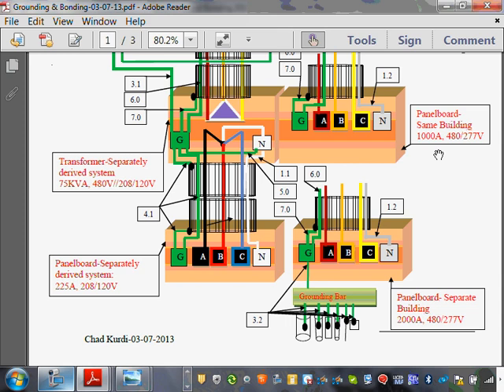So that's the only thing, as close to the source of power. My source of power here is what? My transformer. So bonding at this one would be the preferred method, because you own and operate this transformer too. I mean, it's not, that was a utility transformer, you can't get into that enclosure.